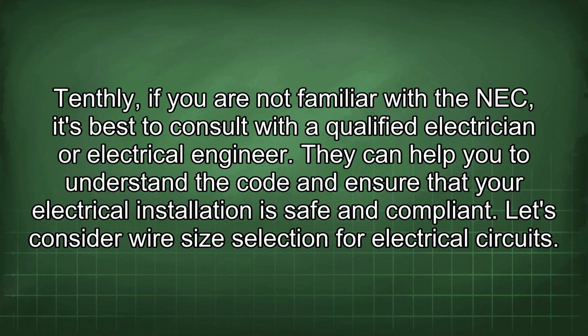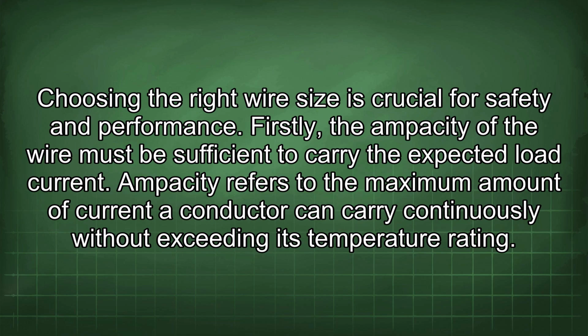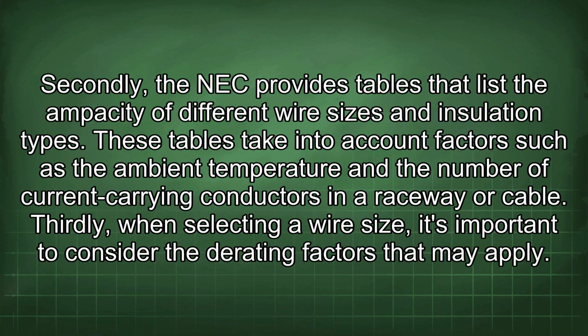Let's consider wire size selection for electrical circuits. Choosing the right wire size is crucial for safety and performance. Firstly, the ampacity of the wire must be sufficient to carry the expected load current. Ampacity refers to the maximum amount of current a conductor can carry continuously without exceeding its temperature rating. Secondly, the NEC provides tables that list the ampacity of different wire sizes and insulation types. These tables take into account factors such as the ambient temperature and the number of current-carrying conductors in a raceway or cable.